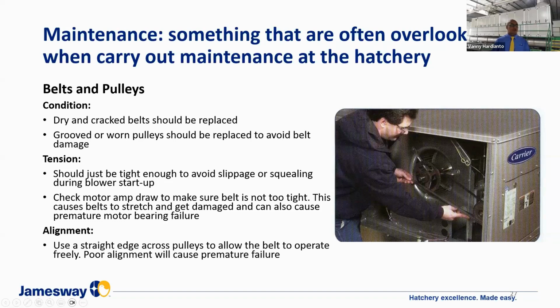You can also check the motor amperes. It will indicate that when your amperage is too high, it means your belt is too tight. The two pulleys should be aligned to prevent premature failure.